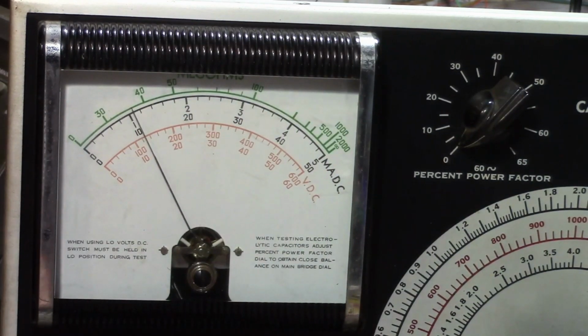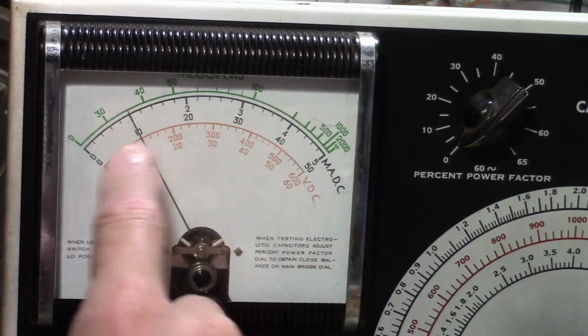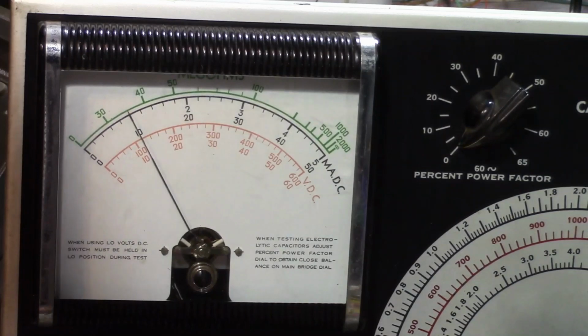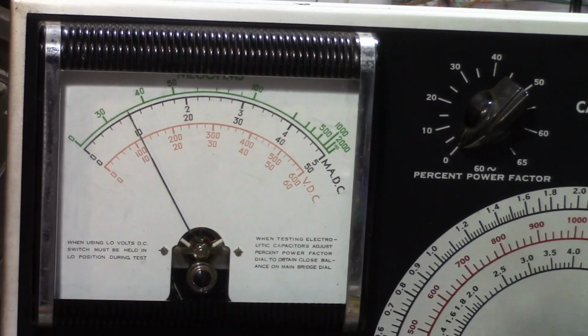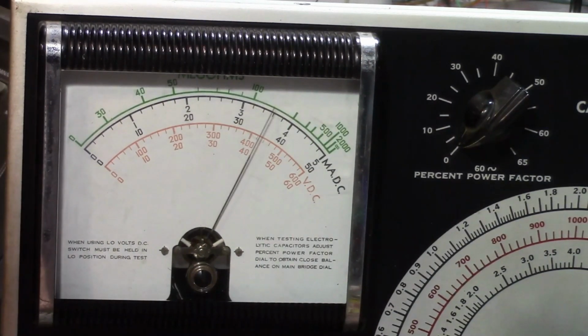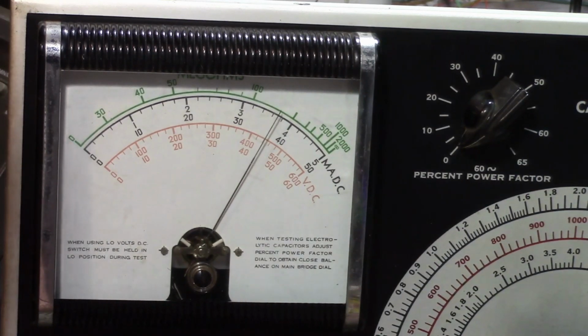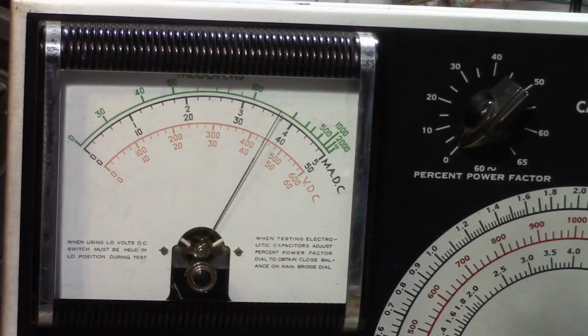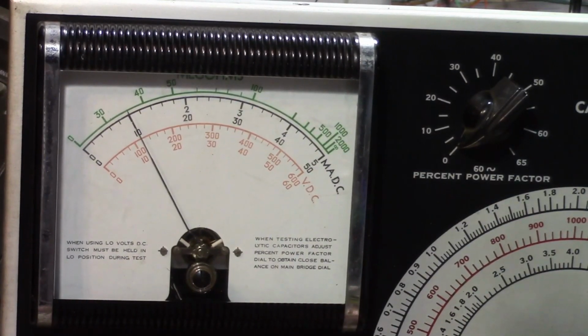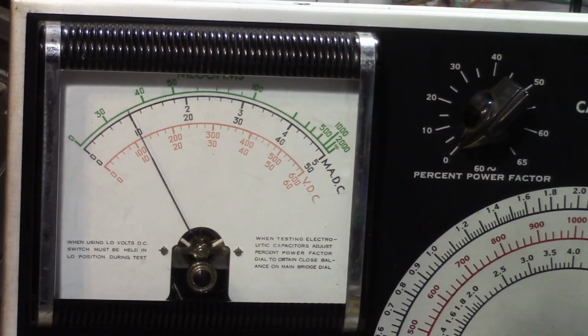So there's a variable knob down here which should go from 0 to 600 volts. Right now it's at 0 on the 600 volt range, so we've got about 120 volts or so. I'll turn it up. I'm now at 300 volts on the knob, and we've got about 450 volts out. This meter is dead on. I compared it to a digital voltmeter, and the two are very much in agreement. So I trust this meter, which means there's something wrong with the variable voltage control.